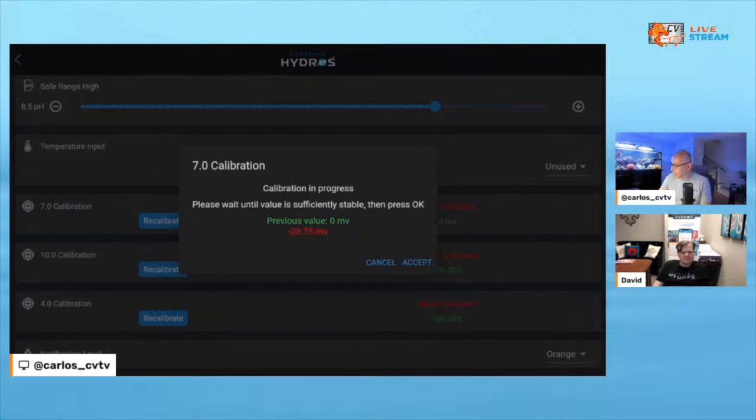You're going to set your clock, and you're literally going to wait 2 minutes. It's going to allow the probe to stabilize. So we're going to let the probe stabilize as much as possible. As you can see on the screen, it started about 25, right, Dave? And now it went to about 10. And now it's at 6.5, and now it's 5. So it's still changing. It's still stabilizing itself. The probe is acclimating to the liquid that is known to be 7.01 pH. So we're just going to keep it at that.